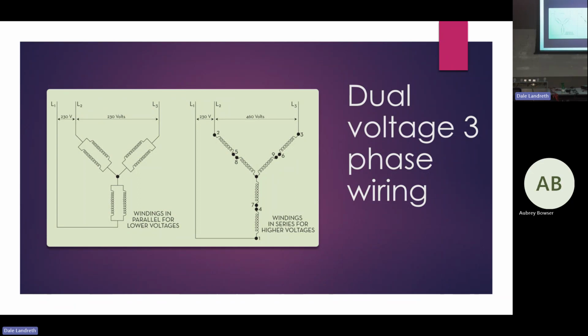So how many windings do we have there? This is a simple question. 6 windings. So we got 1, 2, 3, 4, 5, 6. These 3 right here are tied together internally. All these others is what your leads would be. So if I were to put 460, wired in parallel for 460, what's going to happen? You're going to burn this motor up real quick.